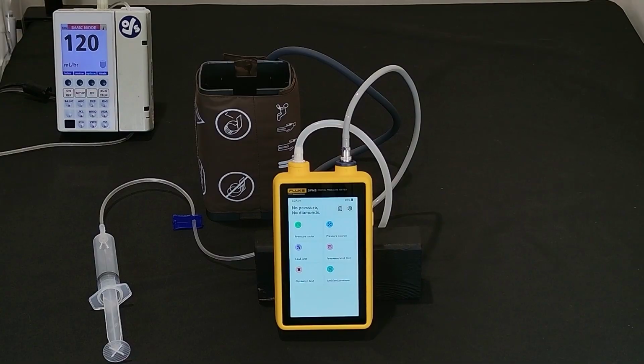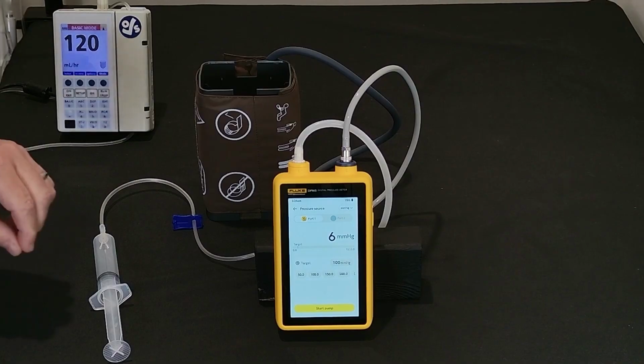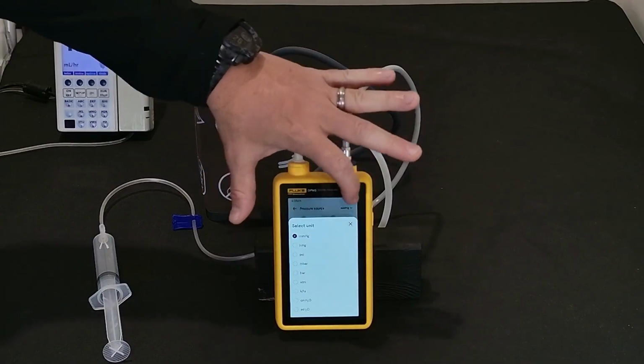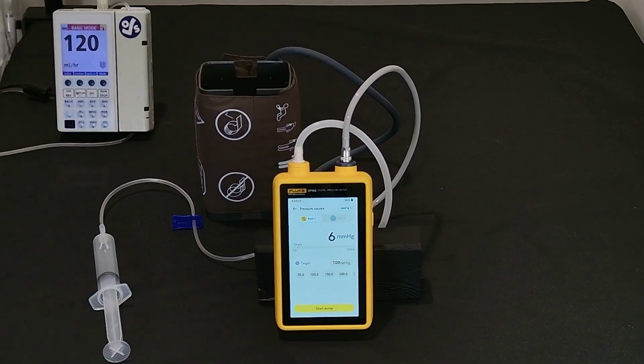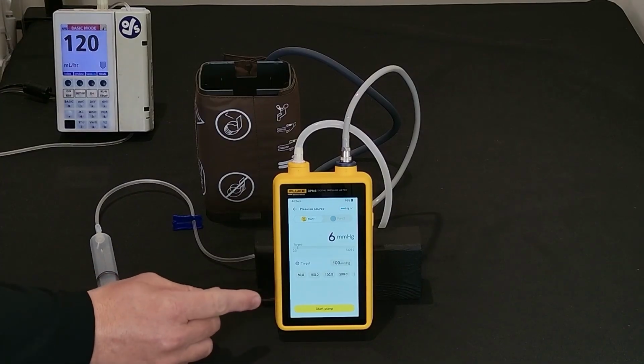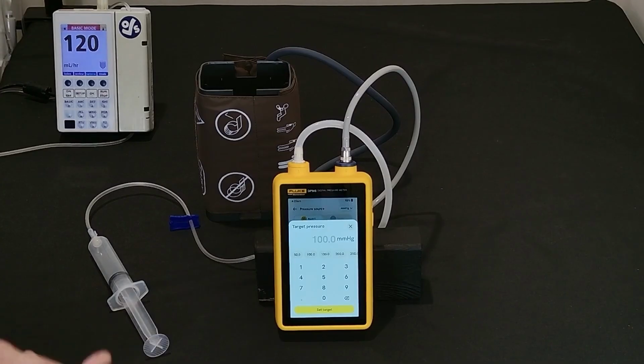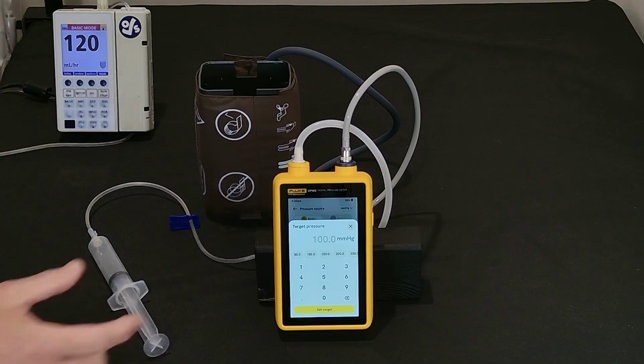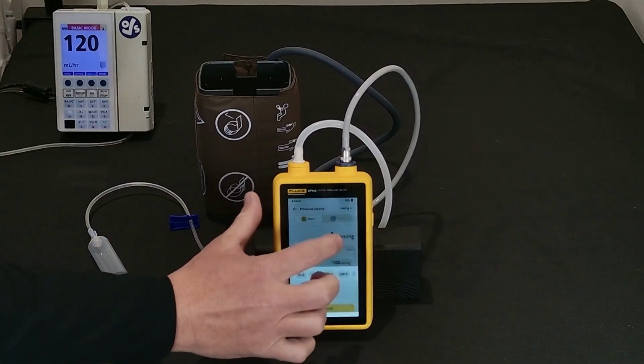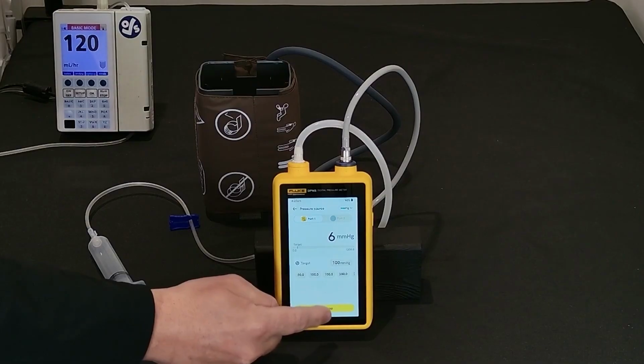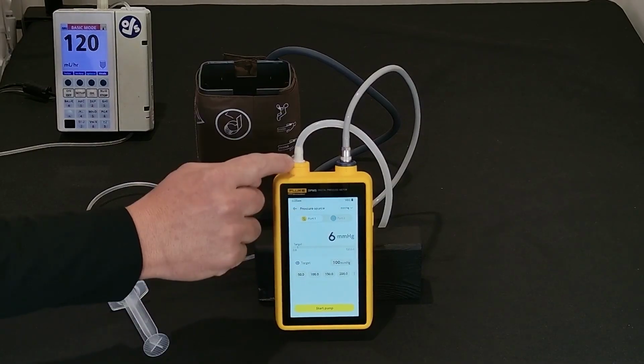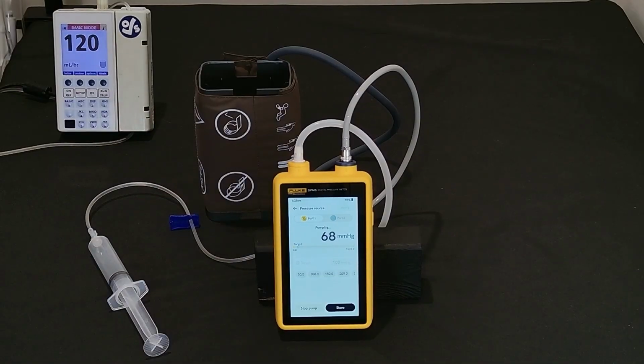Now, let's look at our pressure source. The DPM5 has a built-in pressure pump. Super cool feature. So here, again, we select our units of measurement, which we'll just keep with millimeters of mercury. And then you can select your targeted pressure that your pump wants to pump up to. Here we have some predetermined values, or you can just type in whatever measurement you're looking for. Well, we'll just use 100, and we'll start our pump. Here we're on pump 1, port 1, and we'll start our pump.